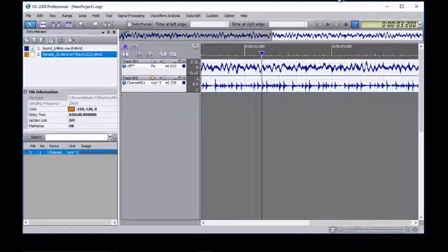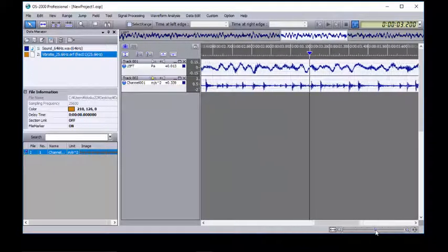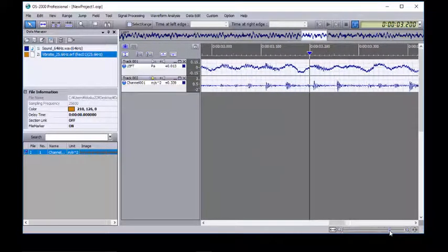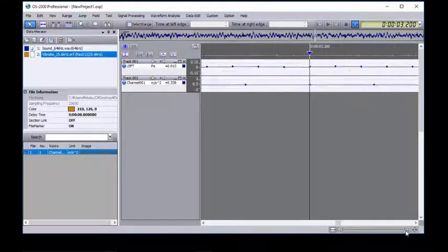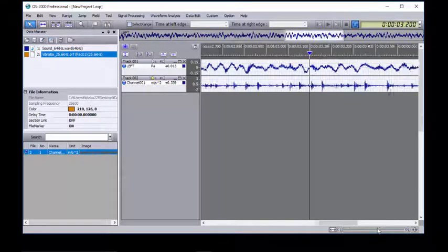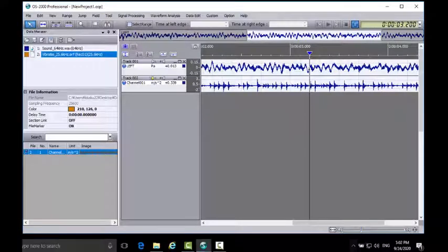One is sound data. The other is vibration data, but taken from the same target. Check if the sampling is really different. Use the slide bar at the right bottom. Moving this bar to the right will enlarge the time-axis waveform. You can see each data has different interval. In this way, the OS-2000 can arrange different sampling data at the same time, and you can compare them.